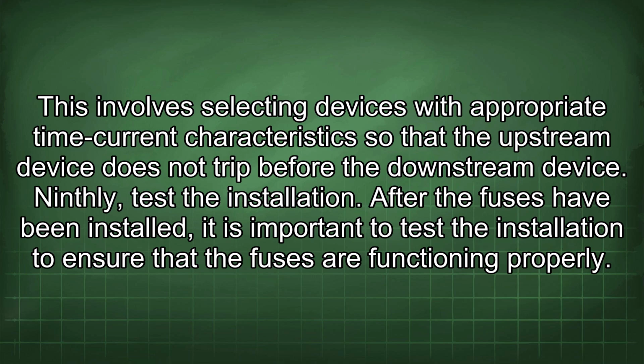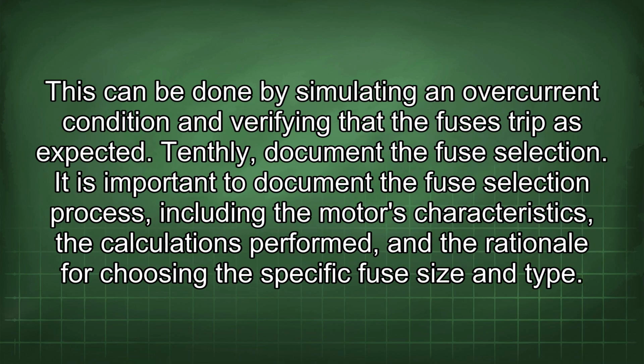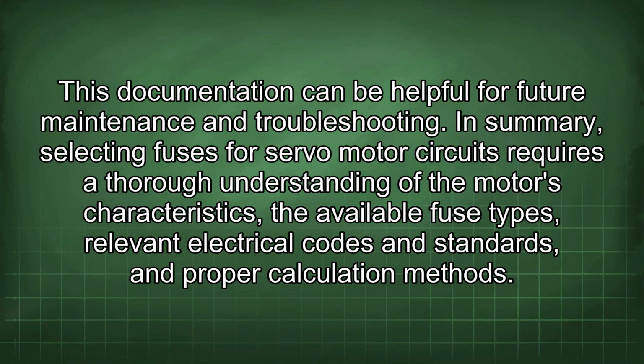After the fuses have been installed, it is important to test the installation to ensure that the fuses are functioning properly. This can be done by simulating an overcurrent condition and verifying that the fuses trip as expected. Tenthly, document the fuse selection. It is important to document the fuse selection process, including the motor's characteristics, the calculations performed, and the rationale for choosing the specific fuse size and type. This documentation can be helpful for future maintenance and troubleshooting.